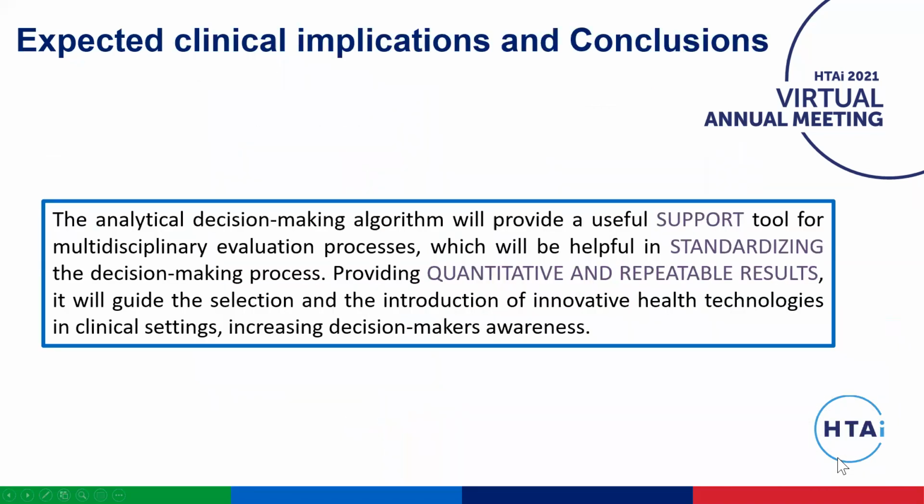The assessment process supported by the algorithm proved to be a helpful instrument in selecting the most suitable patient-specific model. The perfect pacemaker, containing altogether the most appropriate technical characteristics, does not seem to exist on the market. A compromise will be necessary, and the pacemaker model with the highest score will represent the one that includes the highest number of specifications reflecting the most suitable pacemaker for the specific case.